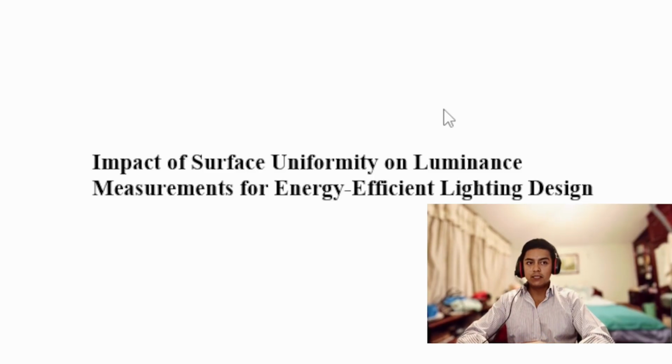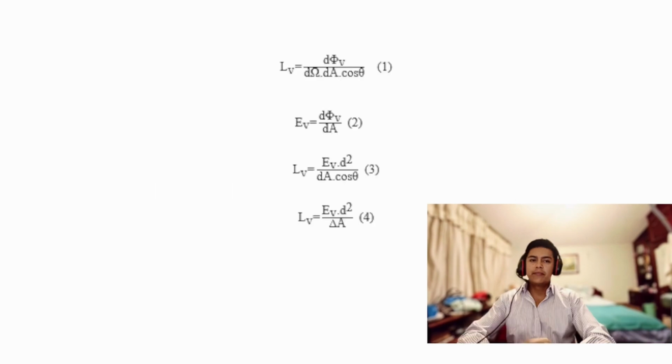On the other hand, a measurement must be accompanied by some quantitative indication of the quality of the result, its measurement uncertainty. Several methodologies can be employed to meet this requirement, with JCGM 100 being one of the most well received by the community due to the endorsement from the CIPM of this procedure. As stated, a viable option for the calibration of both cameras and luminance meters is to assume the lack of luminance uniformity of the illuminated surface and incorporate it as a source of uncertainty in the measurements. This paper presents a methodology for that.